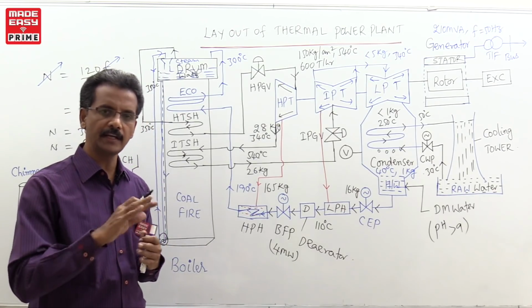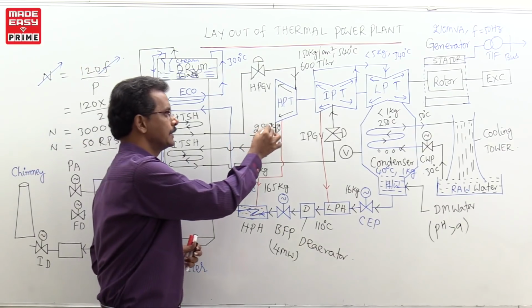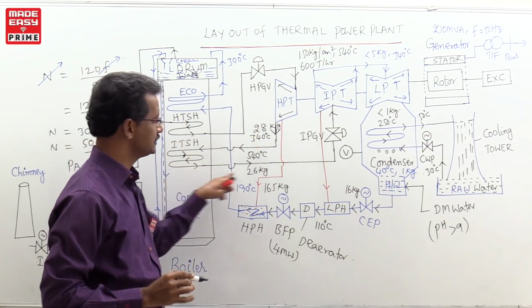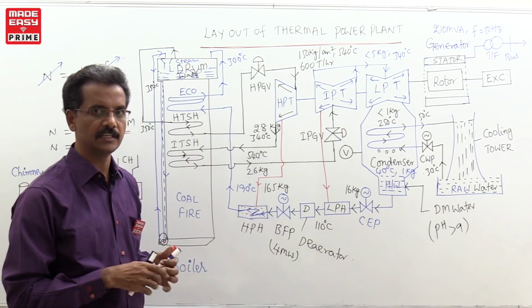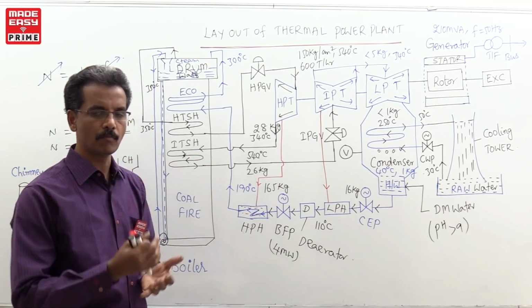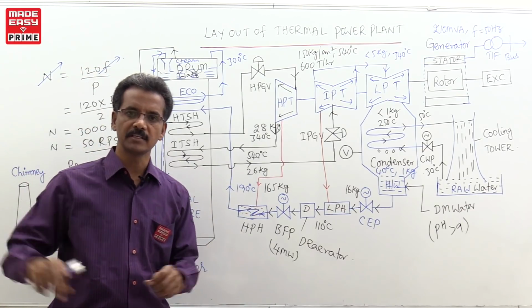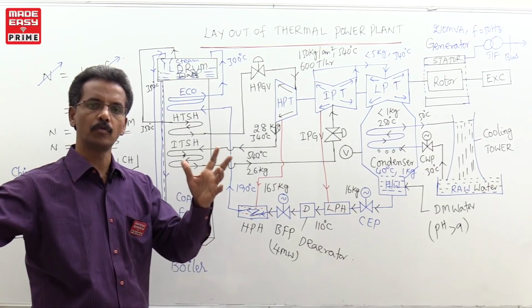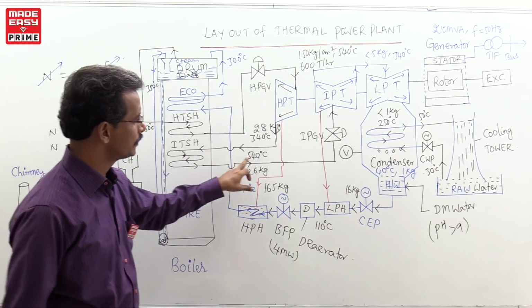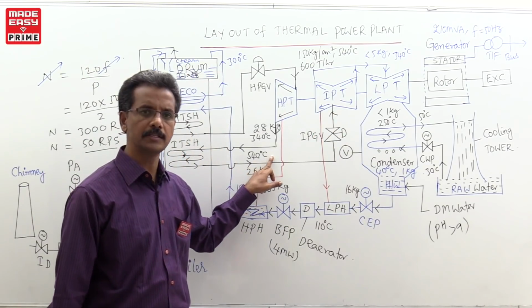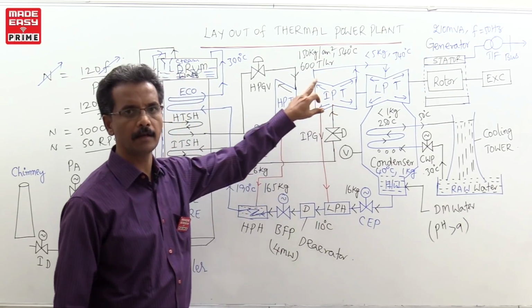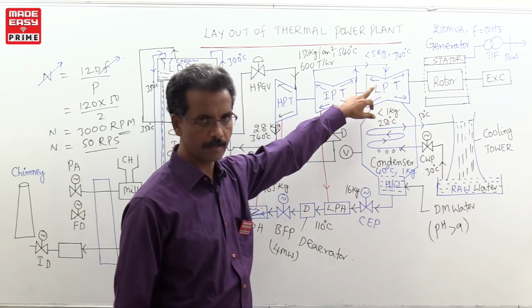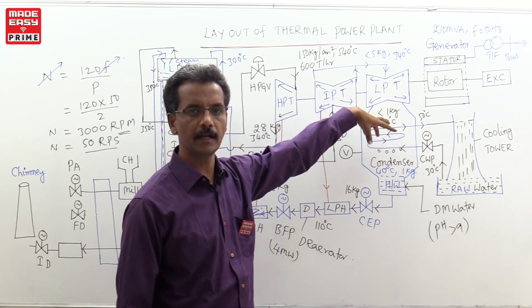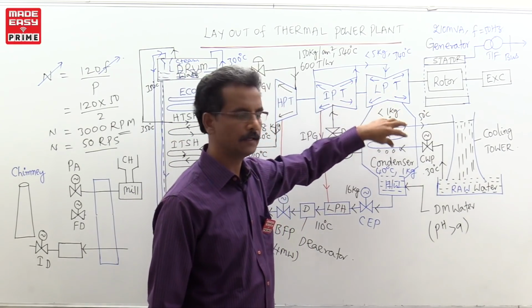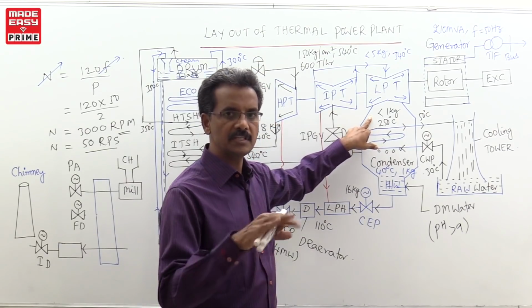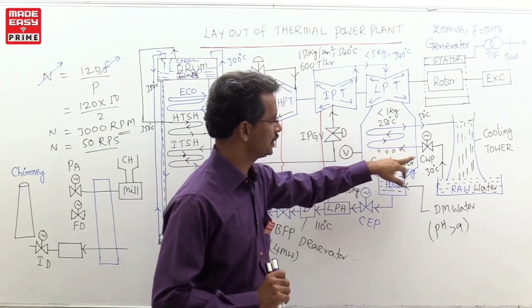If you think of the reheat Rankine cycle or modern Rankine cycle, in the modern Rankine cycle we are using extra reheating, which is done inside the IP superheater, so that the thermal efficiency improves. Mechanical people will know better what the Rankine cycle and the reheat Rankine cycle mean. You can think of the graph between temperature versus entropy; the area, from the energy point of view, will be improved by using this reheating process, right. Now, in this process, when the temperature of the steam is increased, that high temperature steam enters the IP turbine. After work done, the pressure and temperature will be dropped, and it directly enters the LP turbine, and after work done, it enters the condenser. Inside the condenser, vacuum is maintained for improving the efficiency, and this steam under vacuum condition is converted into water by using circulating water.